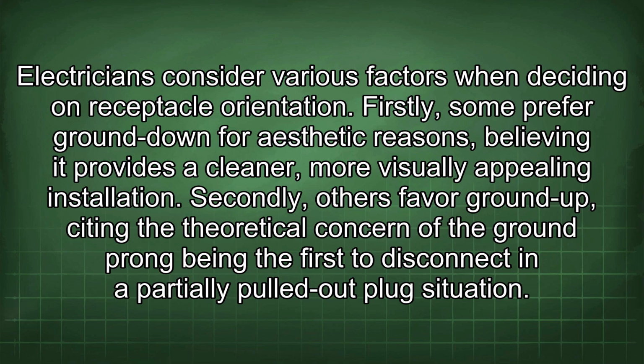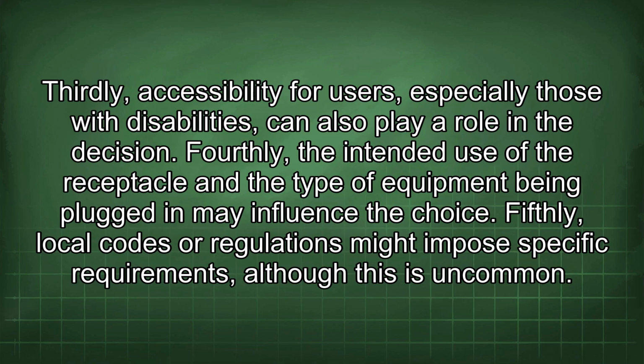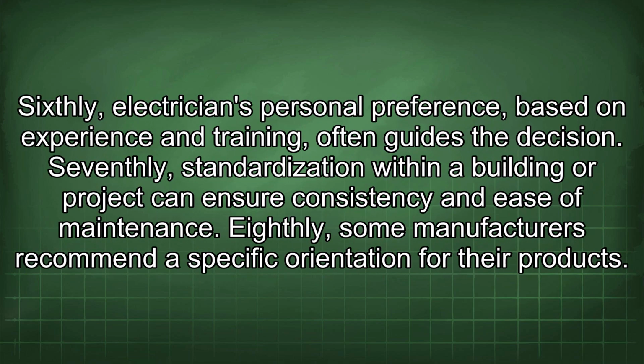Secondly, others favor ground up, citing the theoretical concern of the ground prong being the first to disconnect in a partially pulled out plug situation. Thirdly, accessibility for users, especially those with disabilities, can also play a role in the decision. Fourthly, the intended use of the receptacle and the type of equipment being plugged in may influence the choice. Fifthly, local codes or regulations might impose specific requirements, although this is uncommon. Sixthly, an electrician's personal preference, based on experience and training, often guides the decision. Seventhly, standardization within a building or project can ensure consistency and ease of maintenance. Eighthly, some manufacturers recommend a specific orientation for their product.